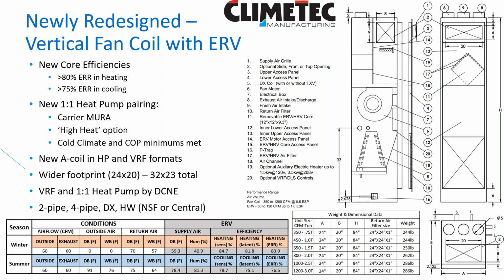And recently we have redesigned this unit to have a higher efficiency. So we can achieve a pretty high enthalpy recovery ratio in heating and in cooling, greater than 80% ERR in heating and cooling. And that's at the design conditions, you can see there at the bottom left. That's at the design conditions that engineers like to design to in Boston. And yes, that means 0 degree outdoor air.